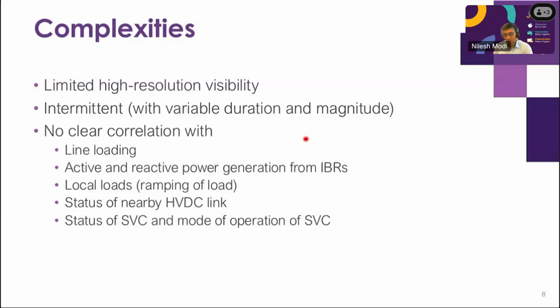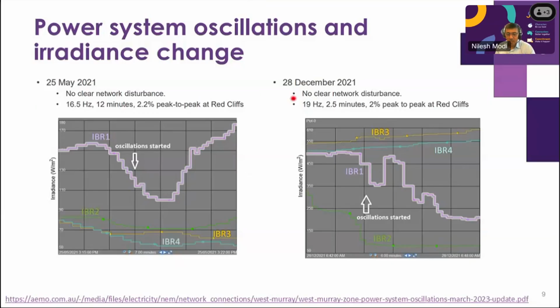So this lists out the complexity we have. It was like a mystery to us until one of the engineers thought, maybe we should start looking at the irradiance. And surprise, what we found is there is a clear correlation between the irradiance change and the onset of oscillation. We started looking at one event, and there was a correlation to it. At one of the IBRs, when the irradiance was dropping, it was coinciding with the onset of the oscillation. We started looking at a number of events, and it was consistent. We looked at almost 8 to 10 events, and almost every time the irradiance at one of those IBRs was reducing, the onset of oscillation was starting.